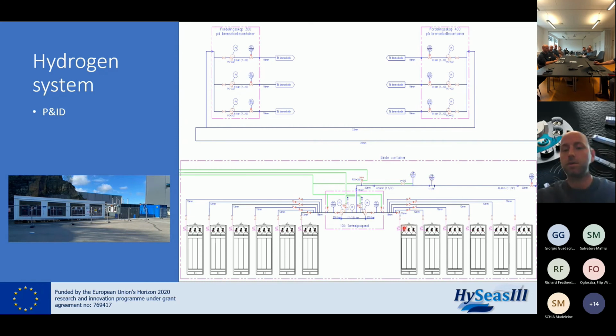You will have valves on the canisters and on the wall, and you will have a main shutoff on the manifold, and you will have a remotely operated ESD valve on the end here. And then you will have the fuel supply lines. So it's actually more than one closed-off valve on this pressure. So the pressure has gone somewhere. We don't know where it's gone, but it's gone somewhere. That's what we indicated with that pressure drop. I hope that answers your question, Giorgio.